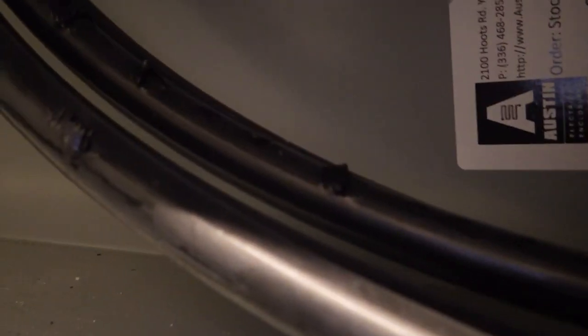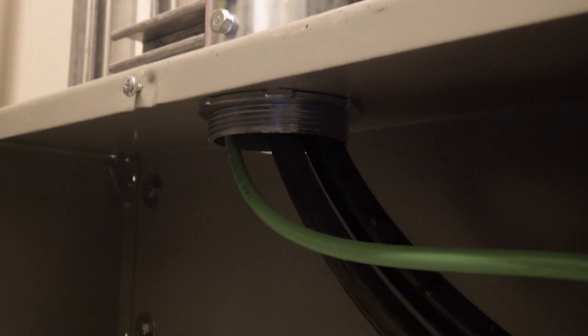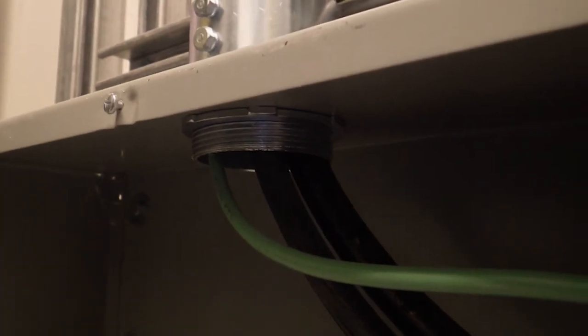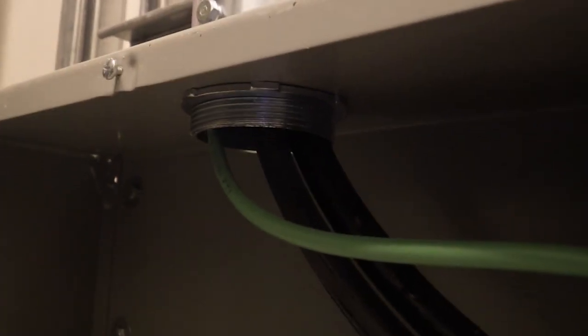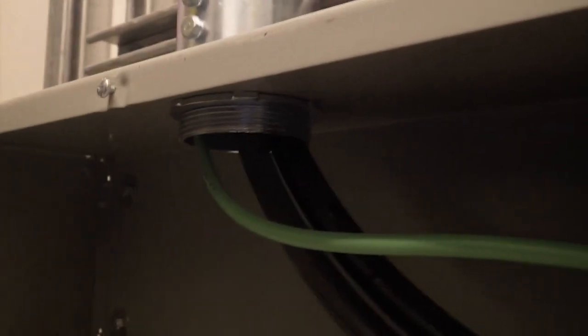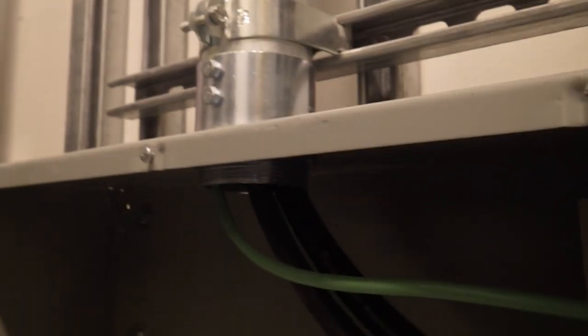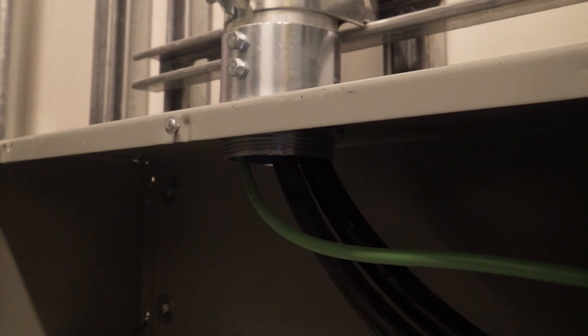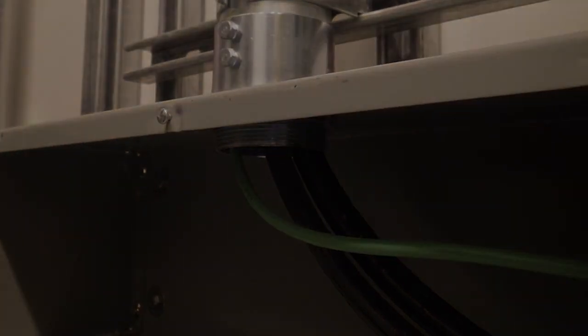And if conductors enter a cabinet, a box, and all your raceways, the conductors have to be protected. And they can be protected with a fitting that has smoothly rounded insulating surfaces, or a listed metal fitting that has smoothly rounded edges, or some other insulated material to separate the wires from the fitting or raceway.